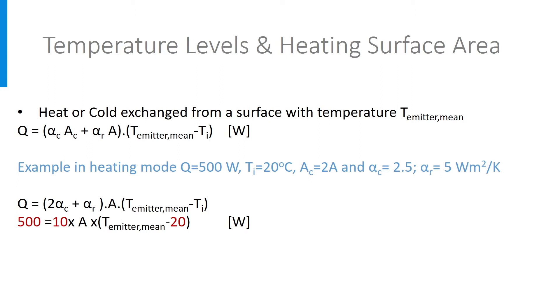This equation gives us some degrees of freedom. At constant heating capacity Q, we can compensate a lower mean temperature of the emitter by a larger surface A. So we can choose many different combinations of radiator size A and average radiator temperature T emitter mean.